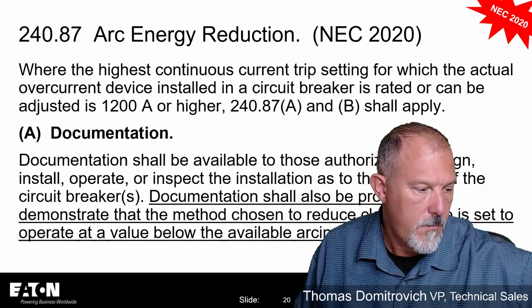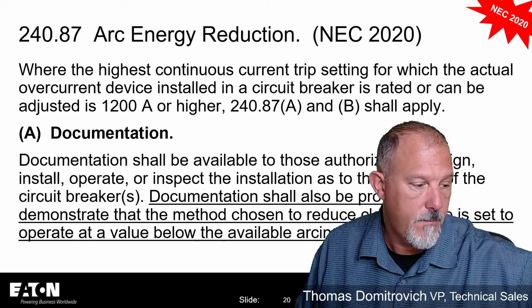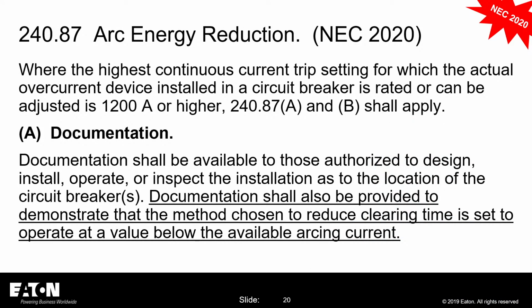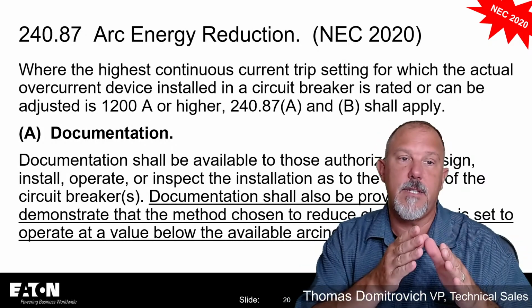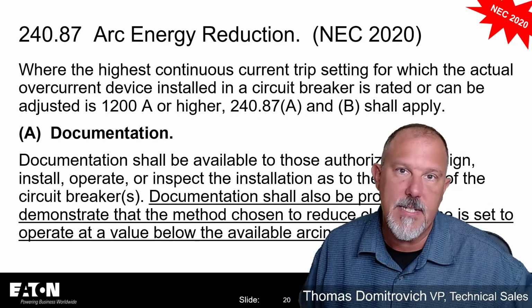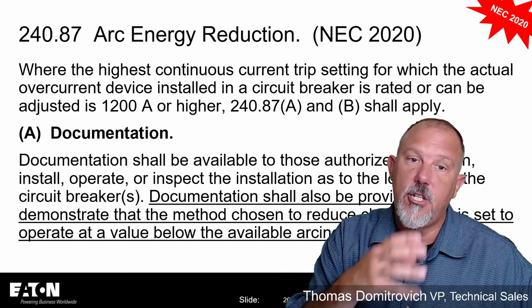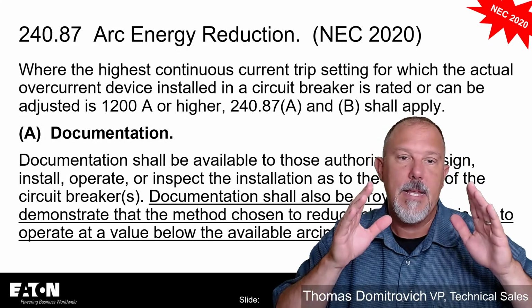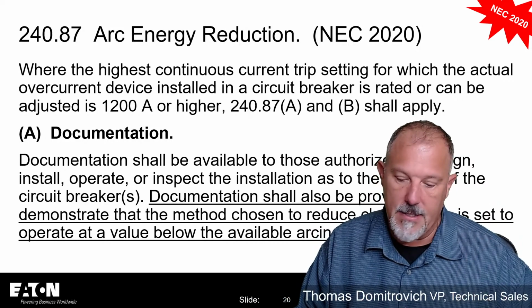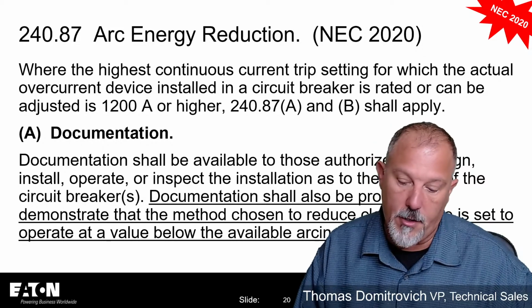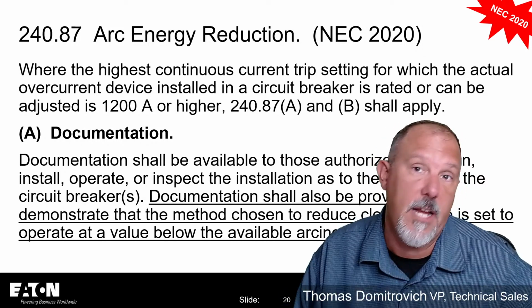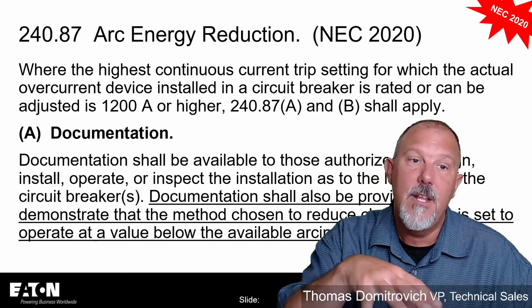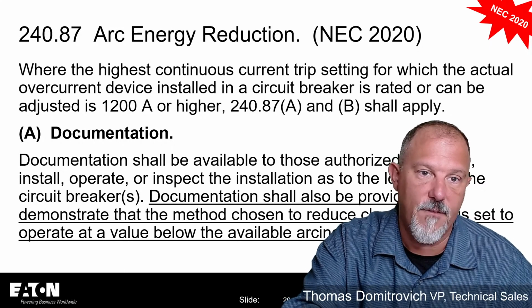It says that documentation shall also be provided to demonstrate that the method chosen to reduce clearing time is set to operate at a value below the available arcing current. Okay, so that is the added meat on the table that the 2020 code brings to the table. You need to show that someone has to calculate your arcing current. Now, it doesn't give you much more guidance than that. It doesn't tell you to use the minimum arcing current, the maximum arcing current, an average arcing current. It doesn't tell you to use IEEE 1584 to calculate arcing current. Someone is going to have to provide that information for you.